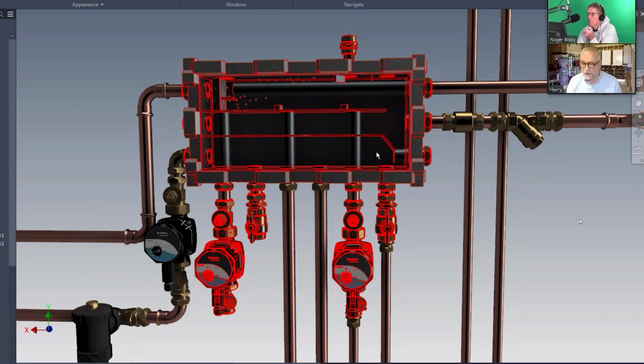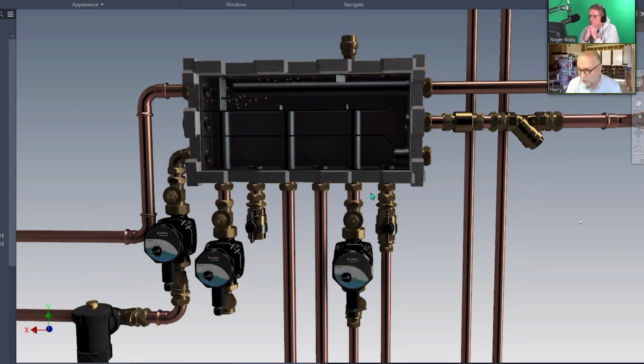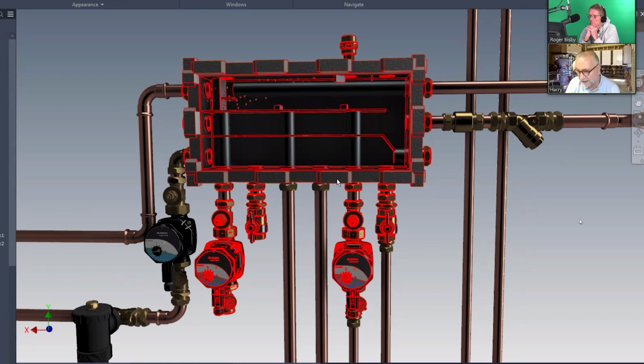The thing that I've noticed people say, they think a pump causes pressure. It causes a differential of pressure. It takes the water from one place, puts it to B, and puts it back to A, if you understand me. So if a pump is badly located and the neutral point is moved into a wrong part of the system, then you get pitching with an open system, or you get air being drawn into a sealed system, and that's where all the hassles come from. People are getting the basics wrong.